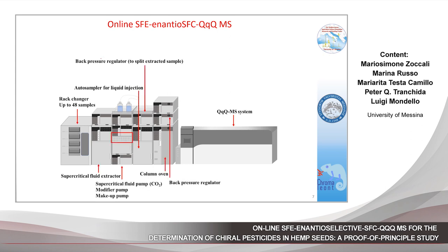The scheme of the employed instrument is here reported. Starting from the left side, you can see a rack changer where you can put up to 48 samples. Then you can see the heart of the system — the supercritical fluid extractor — with three different pumps: the supercritical fluid pump, and two additional pumps that allow modification of the extraction using a solvent with higher polarity to increase extraction of more polar components, and a third pump connected at the end of the analytical column to improve MS ionization. Then you can see a column oven, a back pressure regulator, and finally the triple-quad MS.